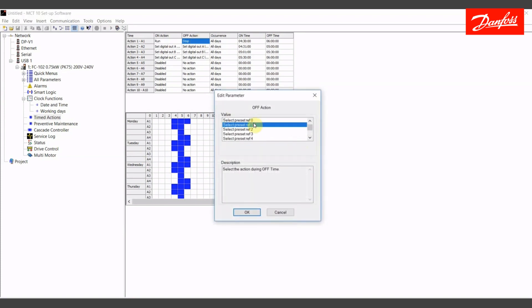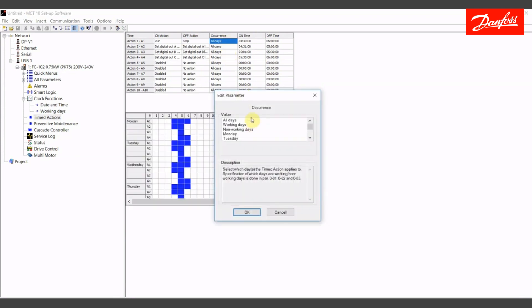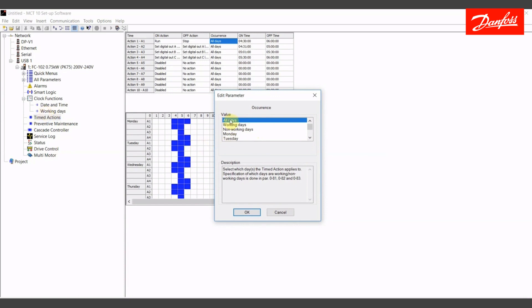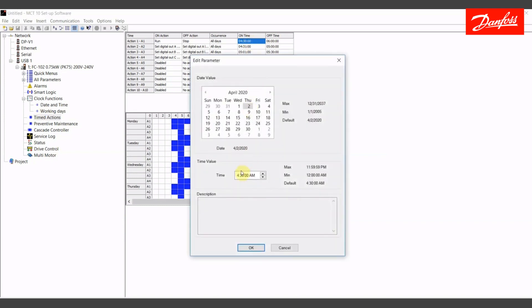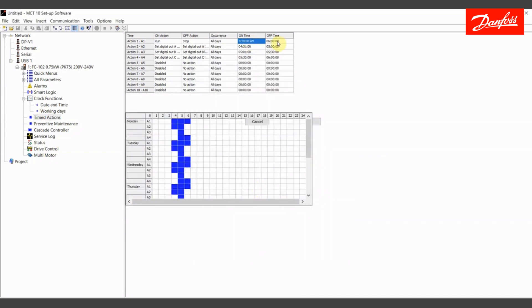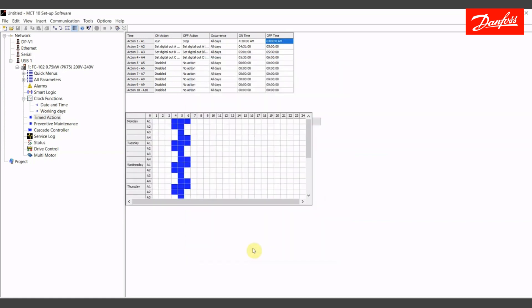If I hit the S key, it'll jump to all the values that begin with S. My occurrence here, I can select working days, non-working days, any particular day of the week. In this case, we're going to go with all days. The working days and non-working days would coincide with what I set up previously in the working day tab. My on time here will be 4:30 a.m. and my off time, 6 o'clock a.m. That's an hour and a half of total run time.